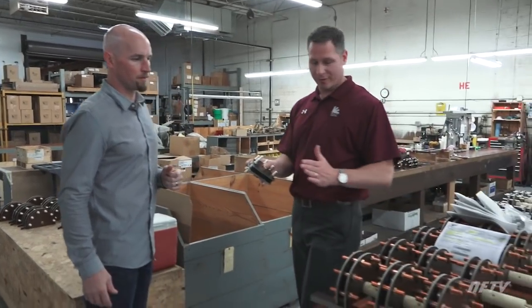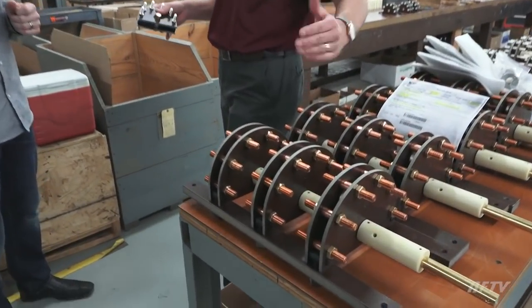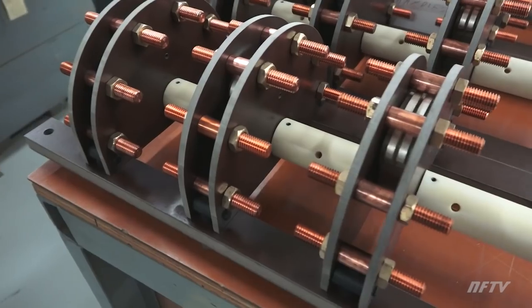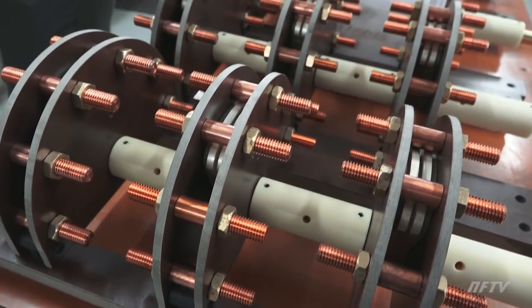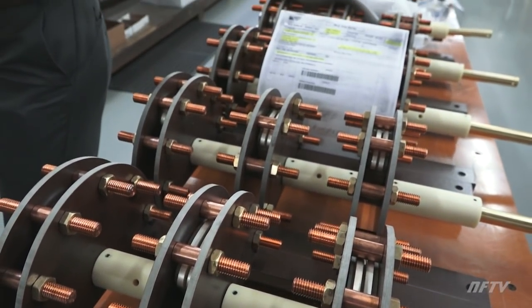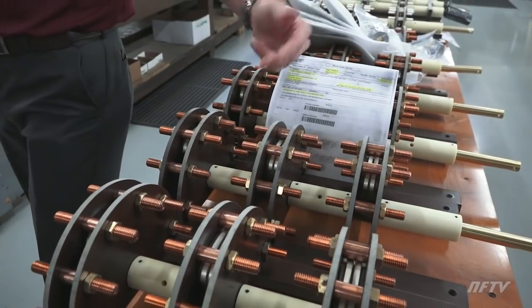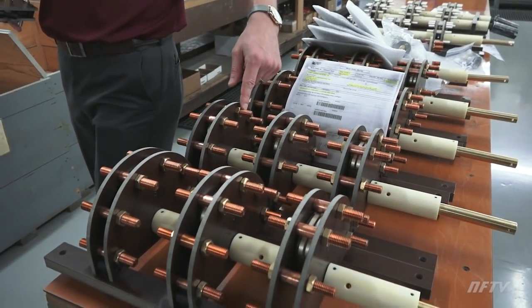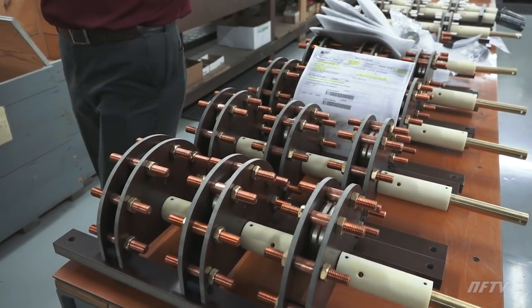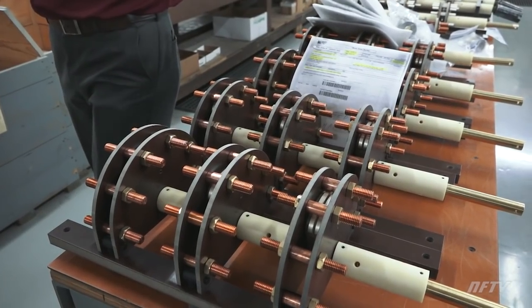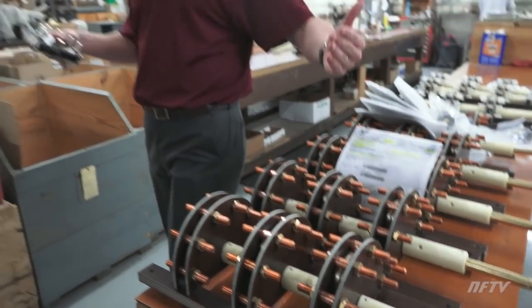We vary the distance between each tap deck, often depending on how big the transformer is and what voltage class it is. If you have more space between the metal component parts, that gives more electrical clearance, so typically the further these are spread out, the higher the voltage switch.